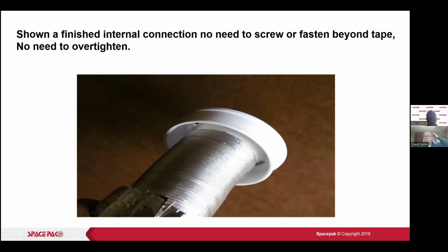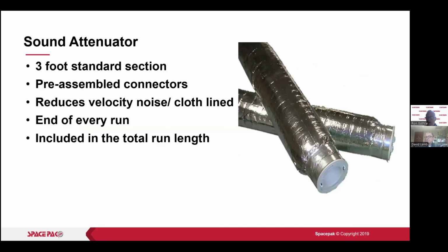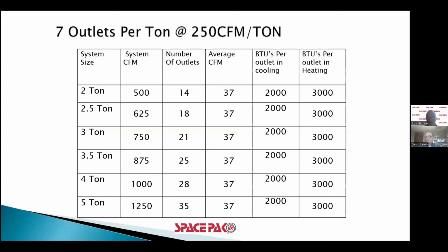All right, the extra insulation gets tucked into here, and you put tape around that just to keep everything tight and secure. Make sure the insulation doesn't pull back off of the aluminum tubing. Here's the sound attenuator, 3 feet long, which comes with the installation kits and goes on the end of every run. If you don't have these on there, it's going to be noisy. You need to have these on there. Think of it as a muffler, if you will.